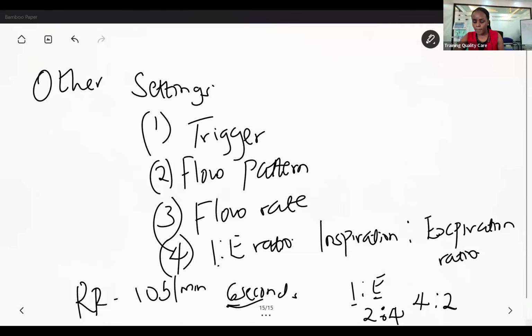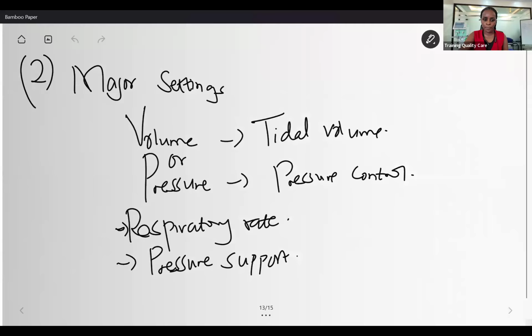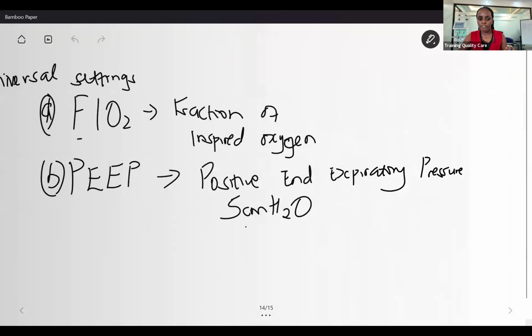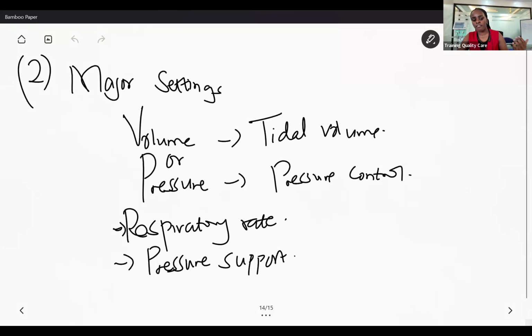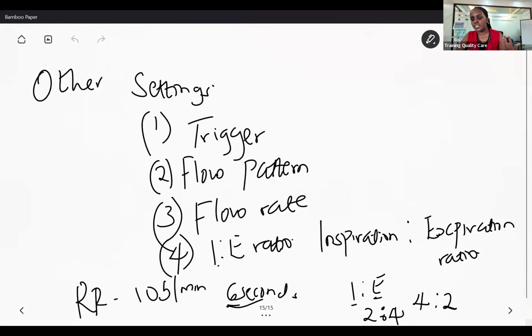So those are the vent settings that we have. We have the universal, that is the FiO2 and the PEEP. Then we have other major settings where we have either volume control or pressure control. We have respiratory rate and pressure support for some modes. And other settings: the trigger, the flow pattern, the flow rates, and the IE ratio. Quickly, I'm discussing some basic vent settings.